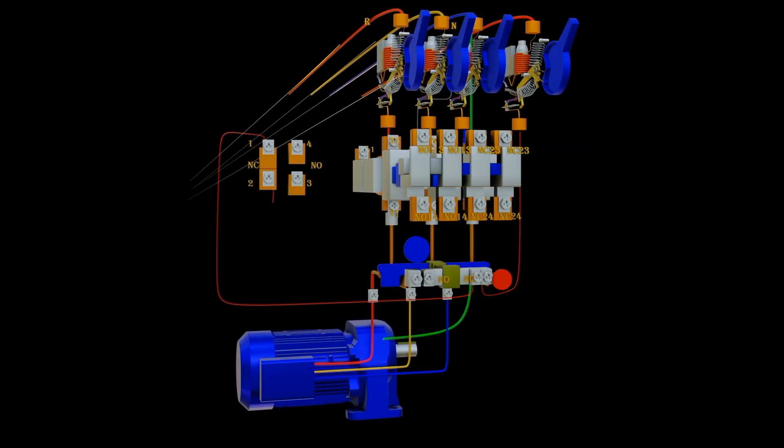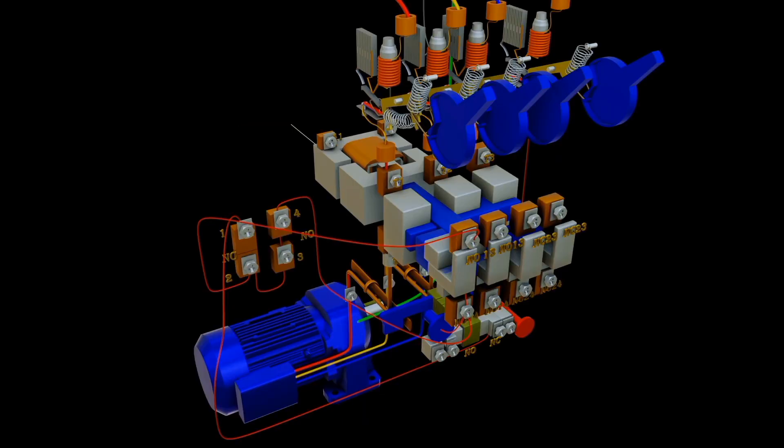Then, from terminal 2 of stop push button, we then connect them in two ways. One is connected to the normally open of push button terminal 3, and the other to normally open of the contactor terminal 13. Then, terminal 4 of start push button is connected to terminal 14, which is looped to terminal A1 of the contactor coil.